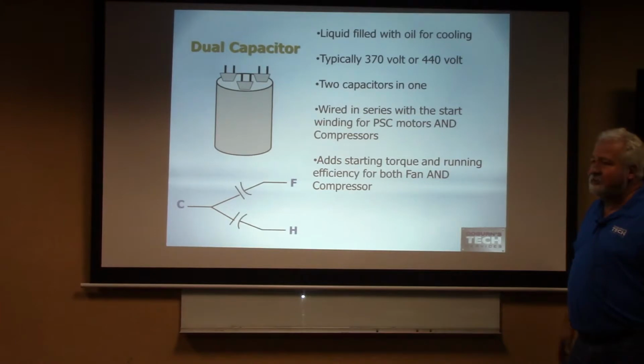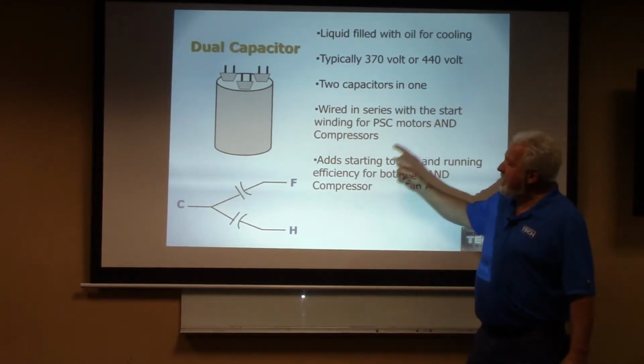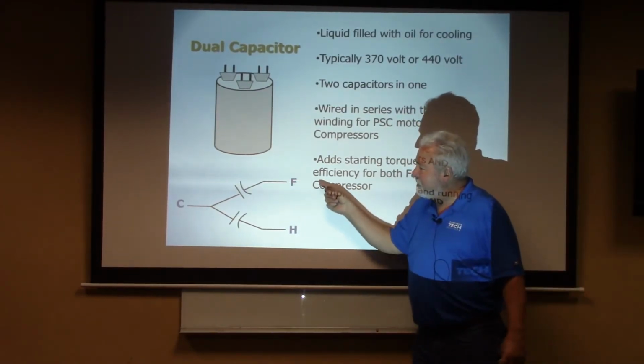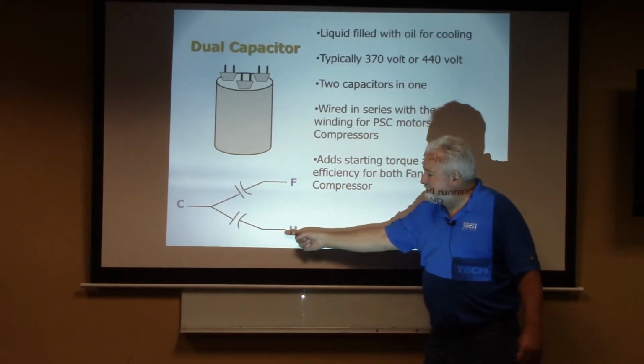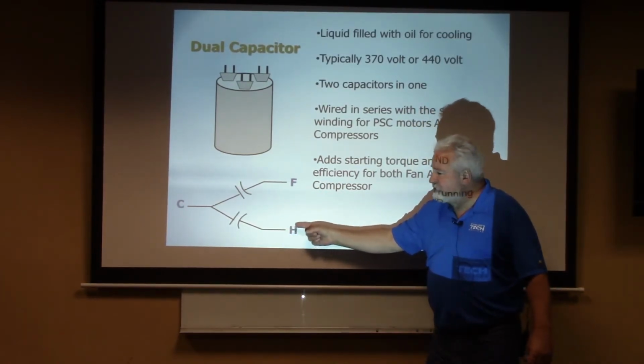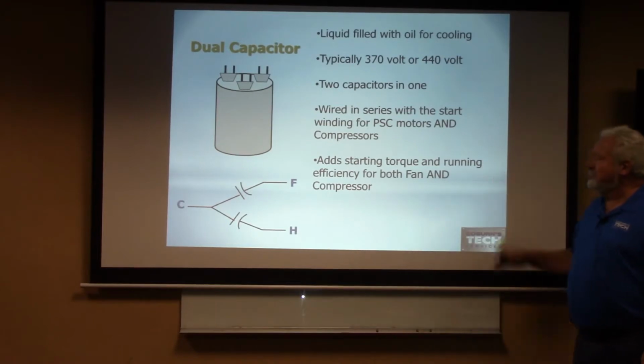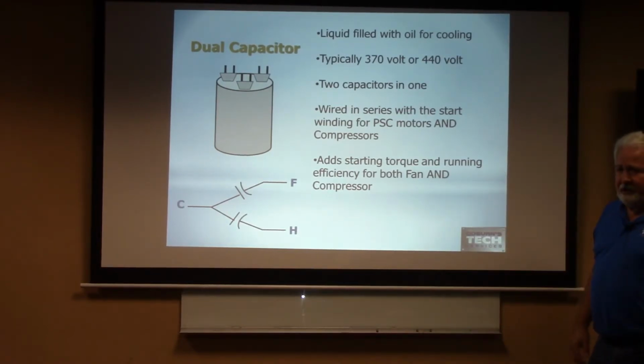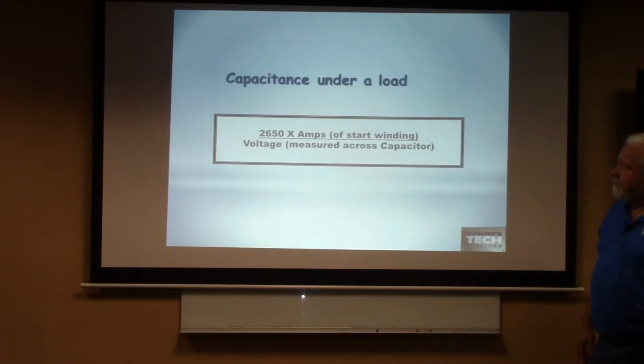It's just two capacitors built into one unit right there. They're still liquid filled. They're still typically 370, 440, two capacitors in one, wired in series with the start winding for the PSC and the compressor. It's wired in series for the fan motor start winding, and it's wired in series for the compressor start winding. It adds starting torque and running efficiency for both the fan and the compressor. Capacitance under a load.